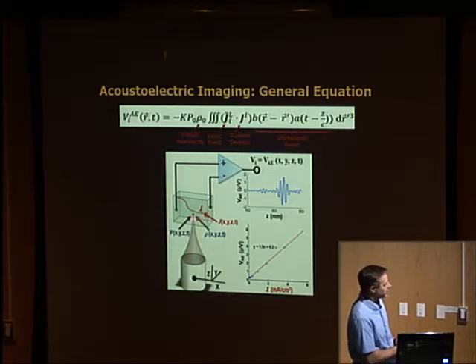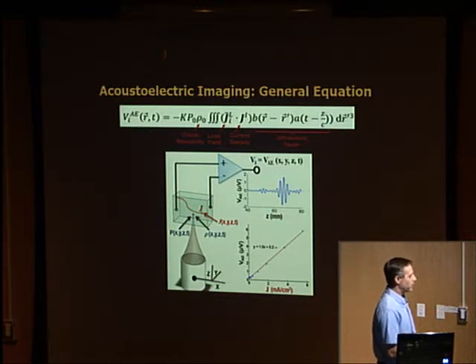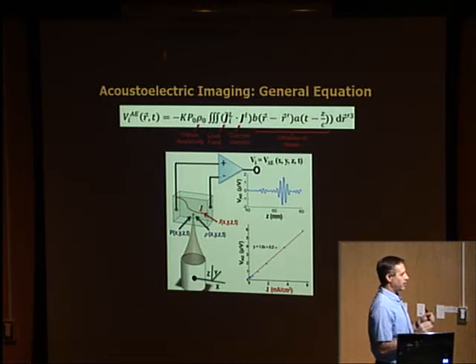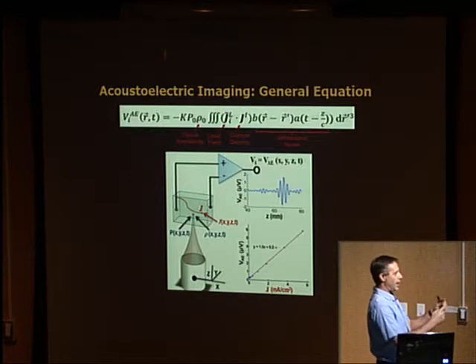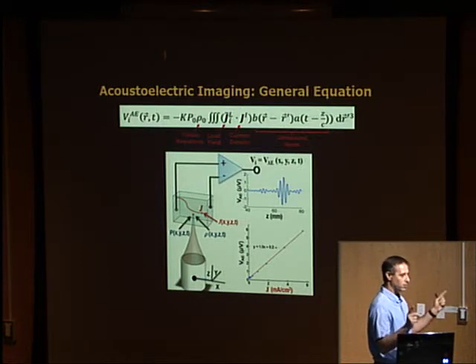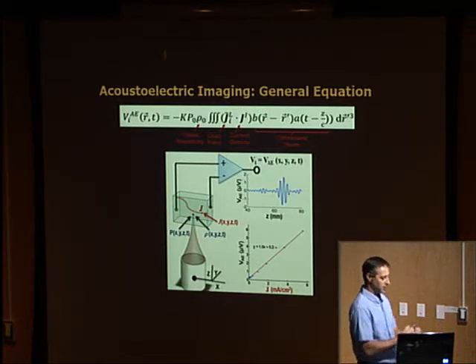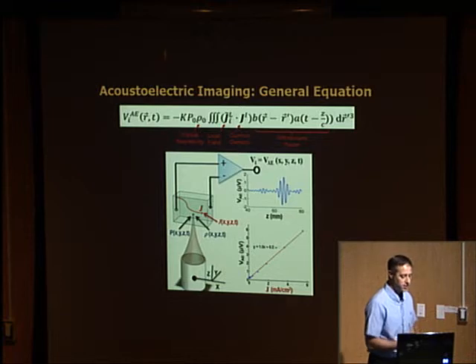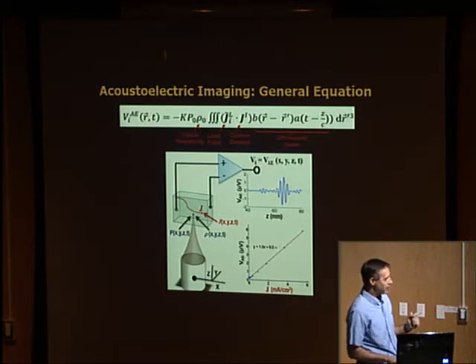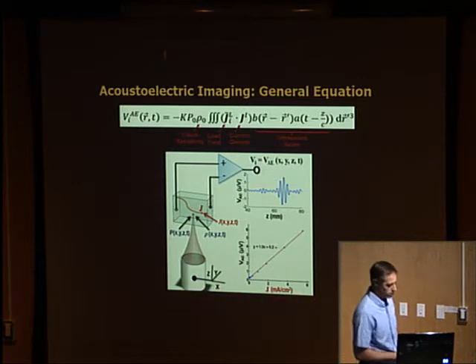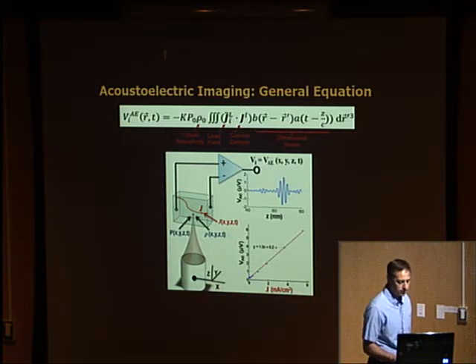This is an example of a waveform that we detect at the right time, which is converted to space by speed of sound, just like with ultrasound. But now I want to make it clear, we're talking about the one-way travel of the speed of sound to the target, and we're detecting the signal on electrodes. So a little different than what I've shown before. The information's coming on these electrodes, and the ultrasound is just transmitting and interacting with the tissue. You can see that V, this voltage, is proportional to J, the current in the tissue.